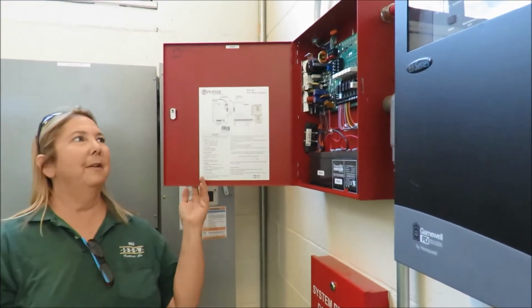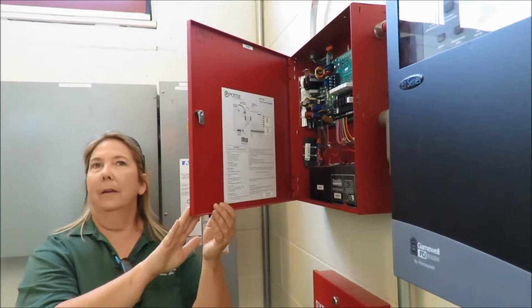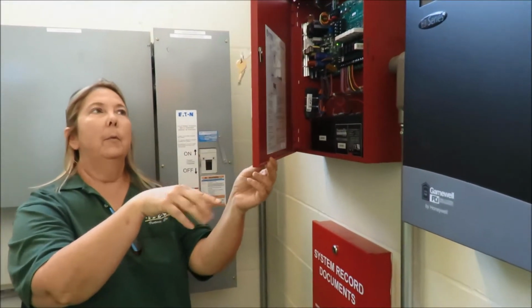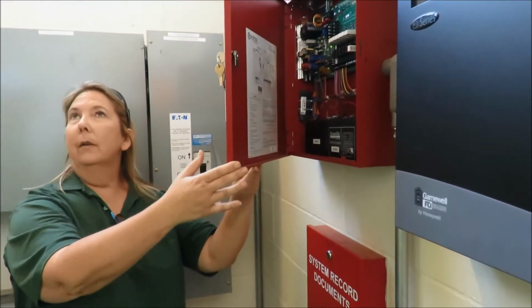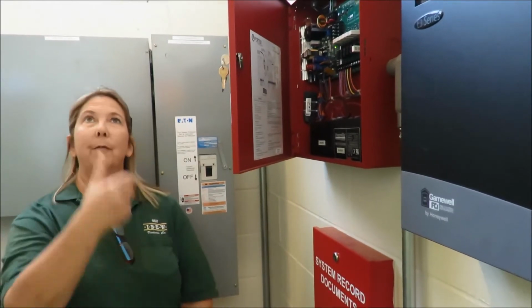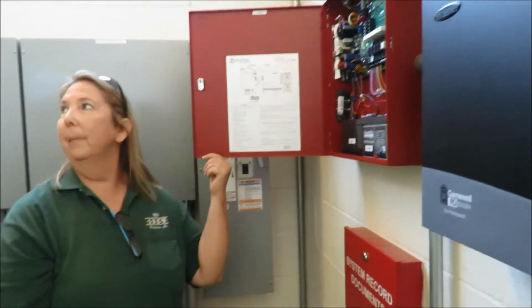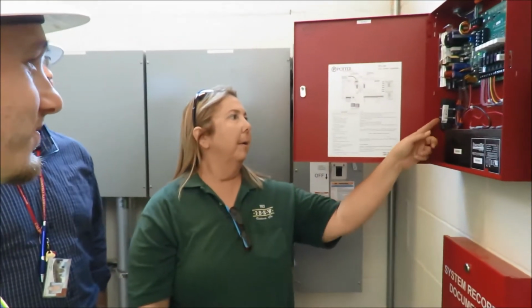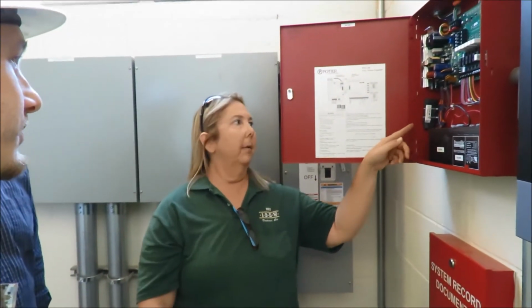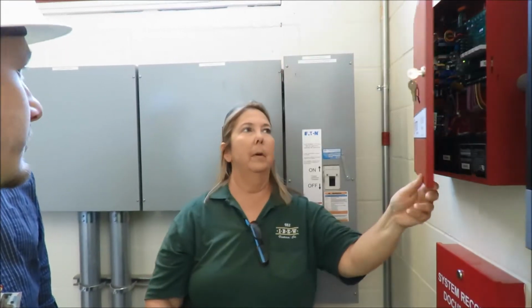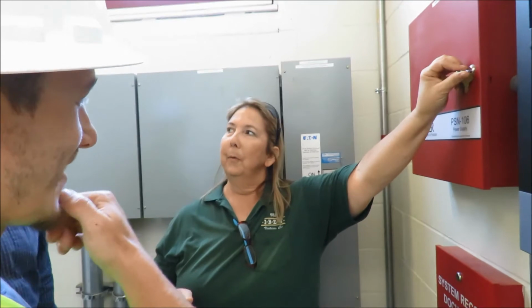When you have multiples, like in the library, it will say we have a trouble on the NAC circuit. So I'm like, okay, it's just like flip a coin. Where do we go? You just start walking until you find the one that gave you the trouble, and hope. But we've also talked about getting an estimate, a proposal, to put these in the library. So things are improving.